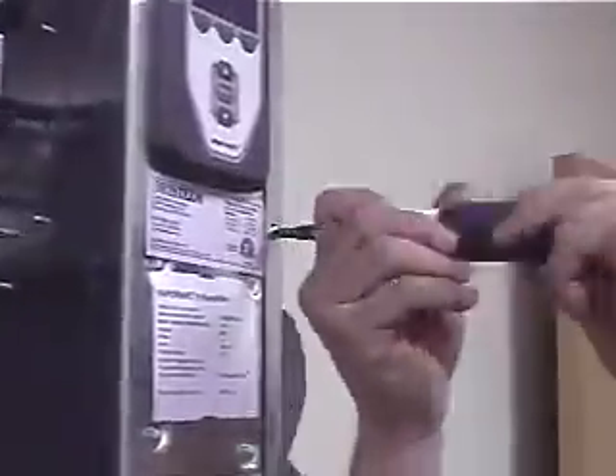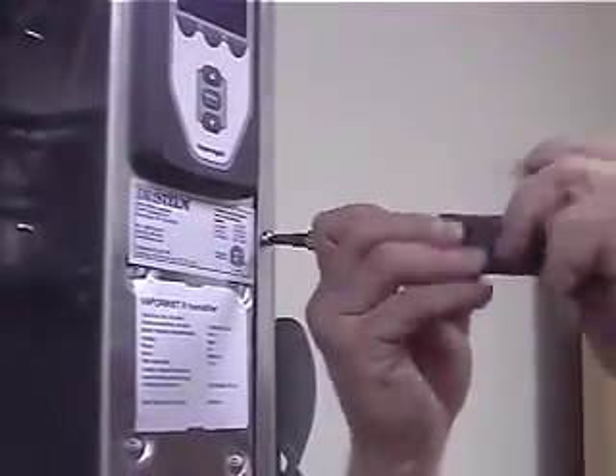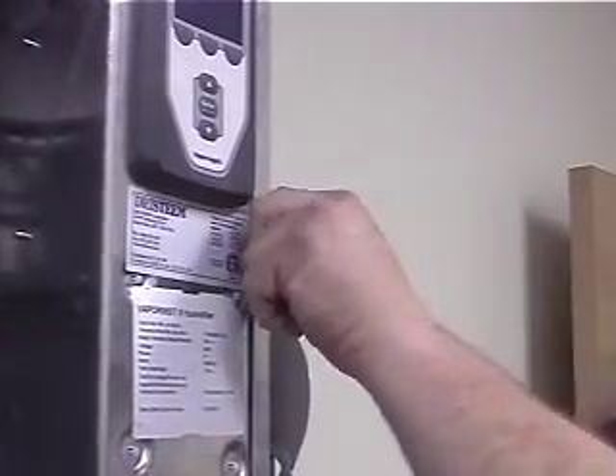In here we're going to get in the controls in just a minute. This one's off in this room, so we're going to go to another room. We're going to get in the controls. I'm going to show you how to go into the diagnostics, how to tell you where everything is basically in them. We can go in, we can actually turn everything on and off one at a time to be able to see what's going on. It's all low voltage on the controls, and then it goes to, of course, a contactor, which then enables our heaters. So all your controls and everything are in this side panel.